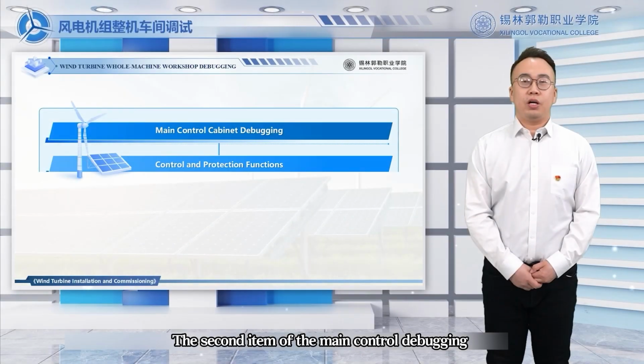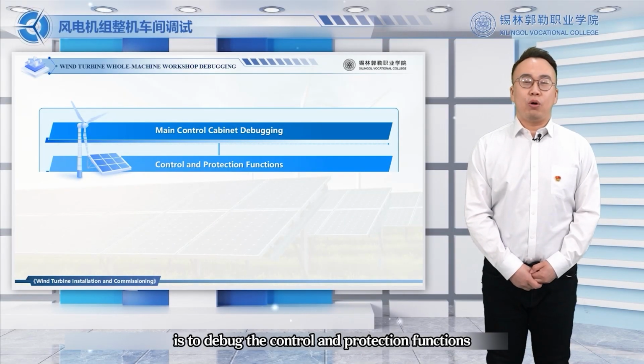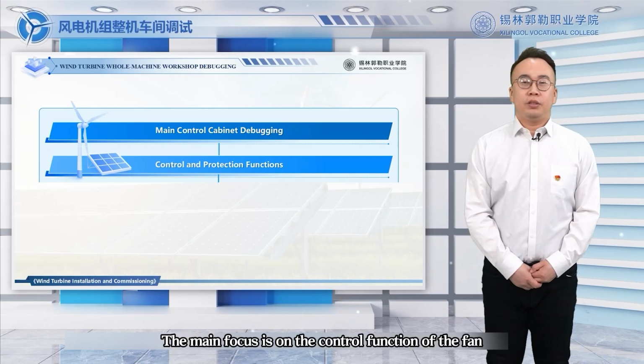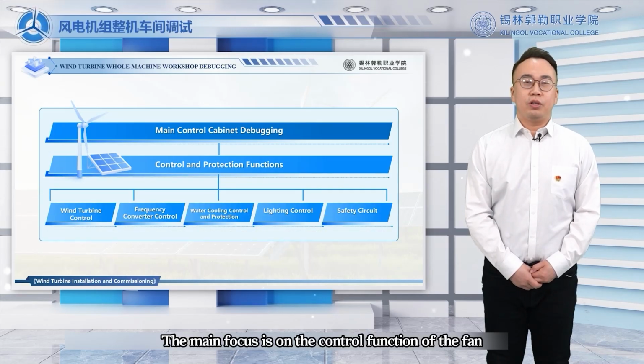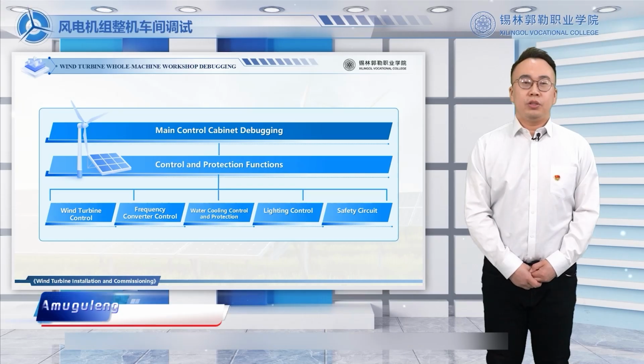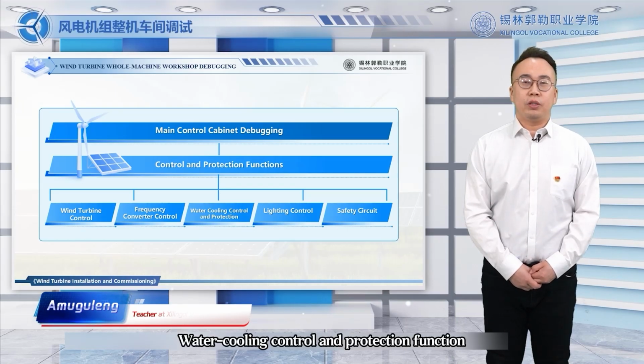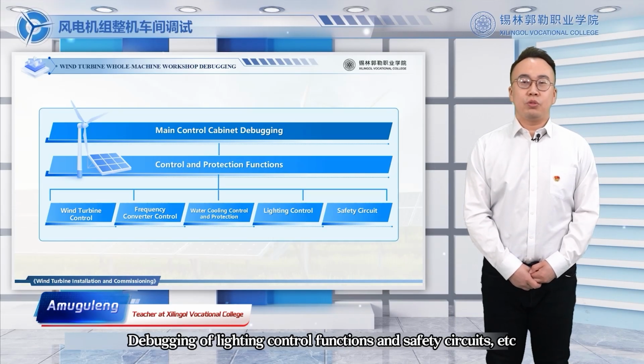The second item of main control debugging is debugging the control and protection functions. The main focus is on the control function of the fan, the control function of the frequency converter, water cooling control and protection function, and debugging of lighting control functions and safety circuits, etc.